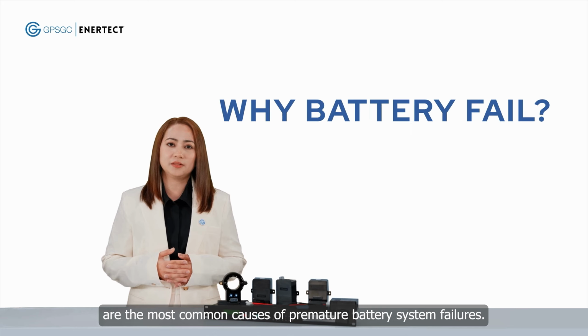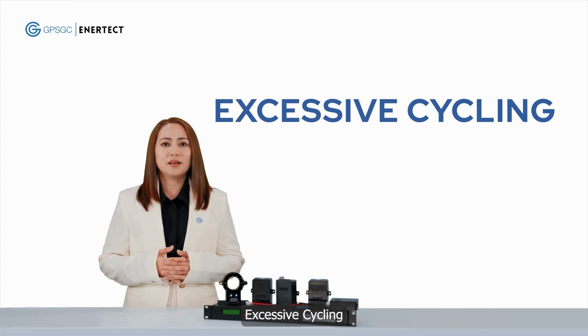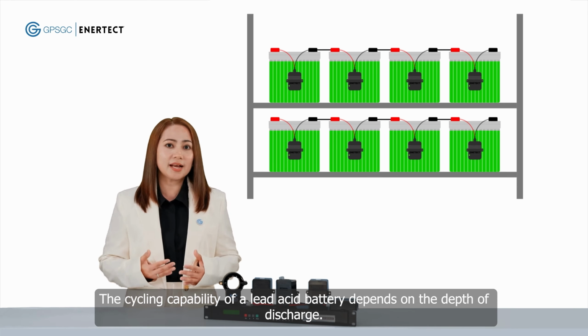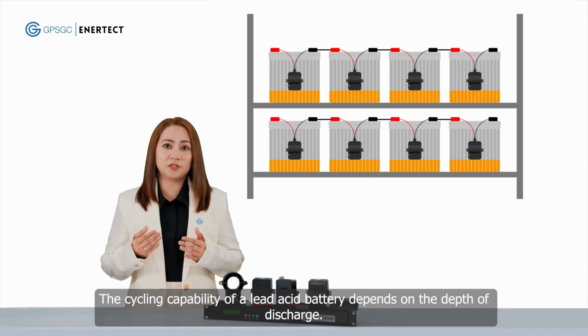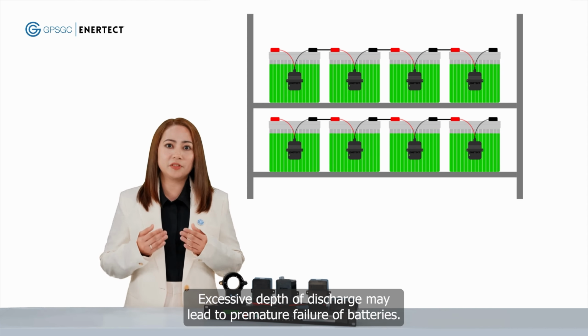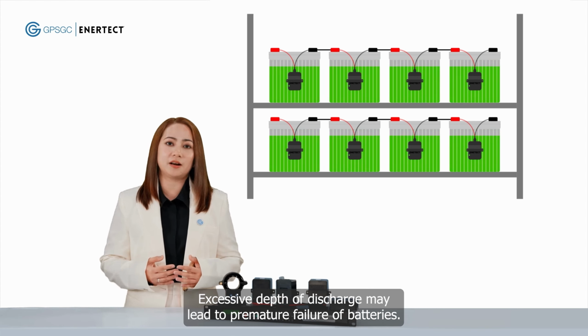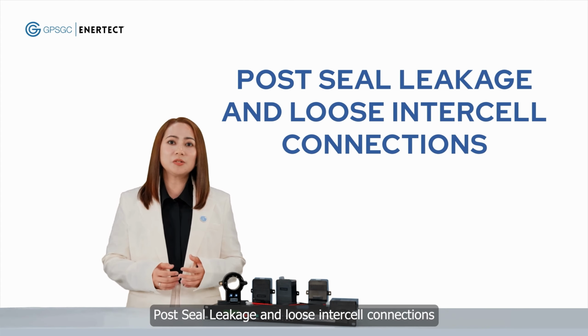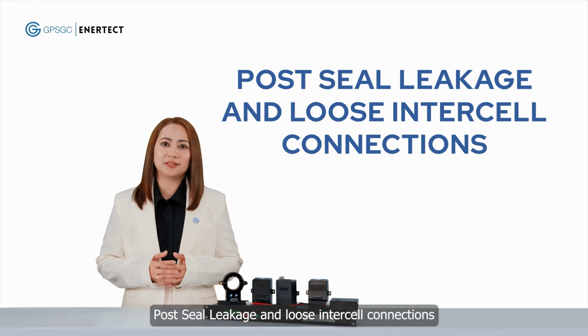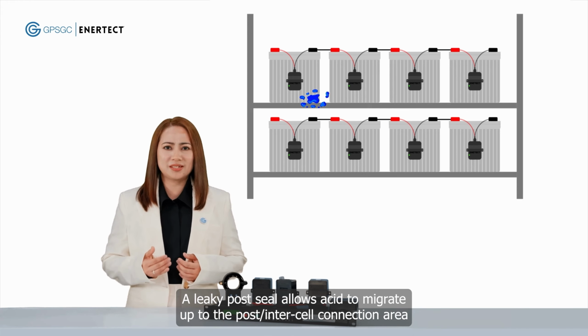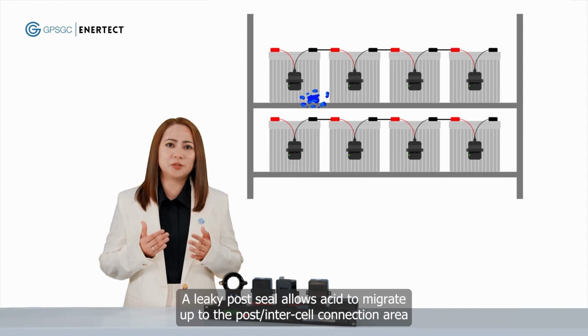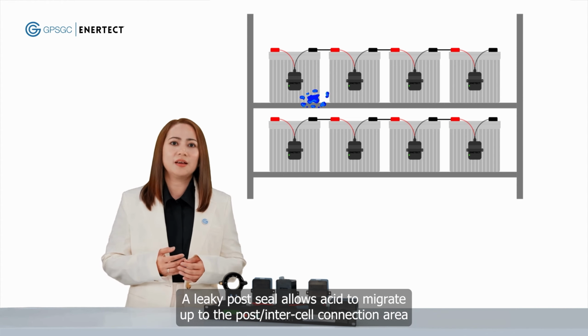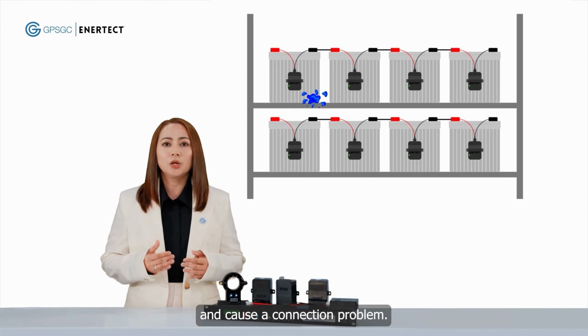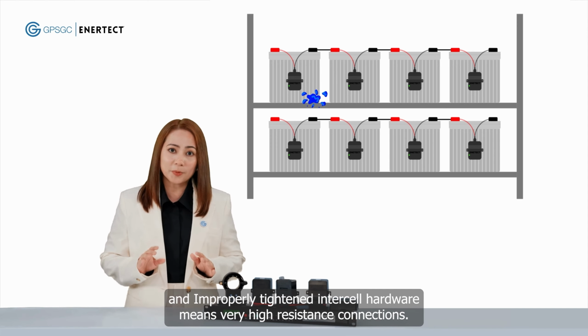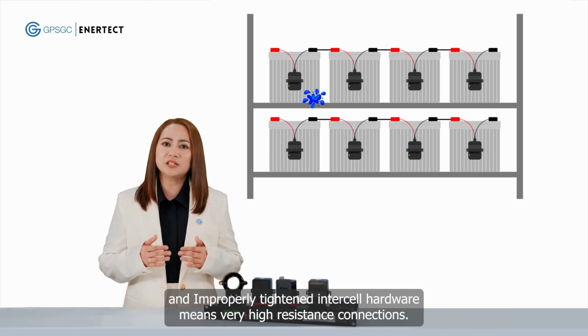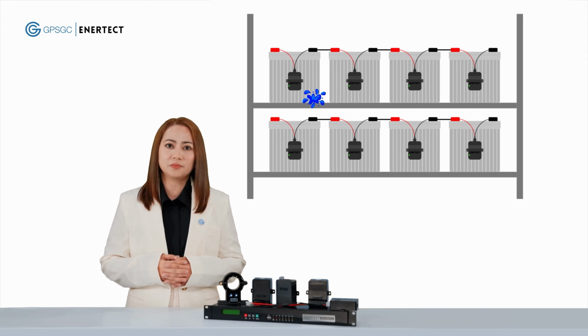Excessive cycling. The cycling capability of a lead-acid battery depends on the depth of discharge. Excessive depth of discharge may lead to premature failure of batteries. Post-seal leakage and loose intercell connections. A leaky post seal allows acid to migrate up to the post or intercell connection area and cause a connection problem. Loose intercell connections and improperly tightened intercell hardware means very high resistance connections.